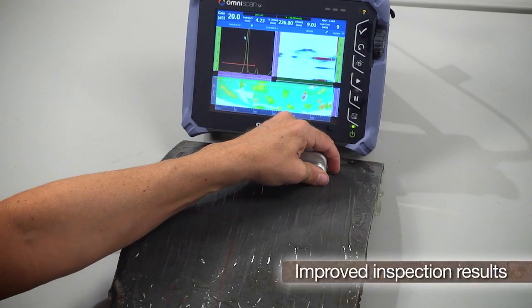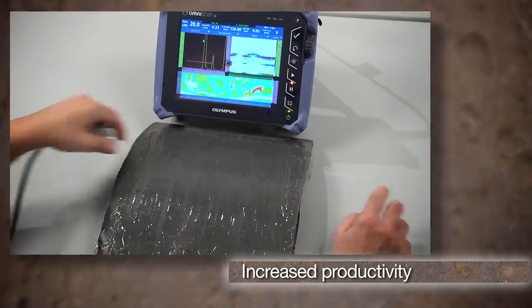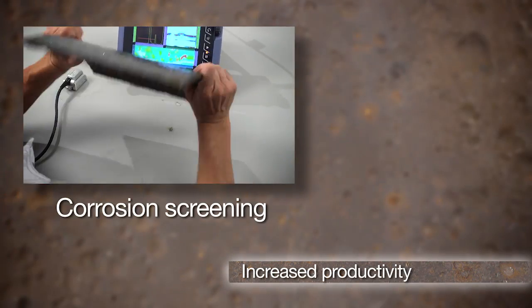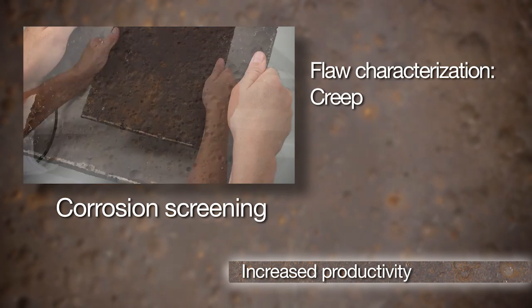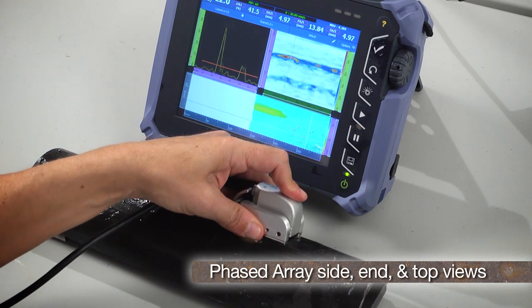The dual-linear array probe provides improved inspection results and increased productivity for corrosion screening and characterization of flaws such as creep, HIC, and pitting, by use of phased array side, end, and top views.